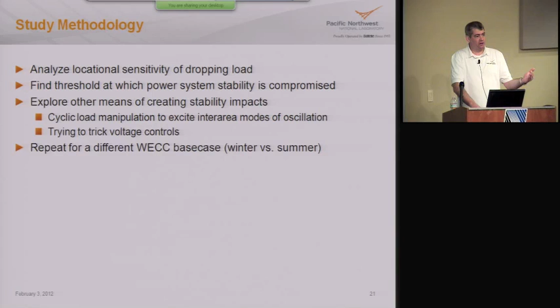I repeated this for another case. The first plots I'll show are the summer case. This plot shows the same amount of load shed in different locations, 10 seconds into the simulation. Clearly, there was one location—this top trace—where the system was much more sensitive to that amount of load drop compared to the other locations shown at the bottom. A trained observer will also notice that the system dynamics stirred up are different; this is the frequency of the actual oscillation of the waveform. There's a difference between where in the system you drop the load and what the dynamic response will be.